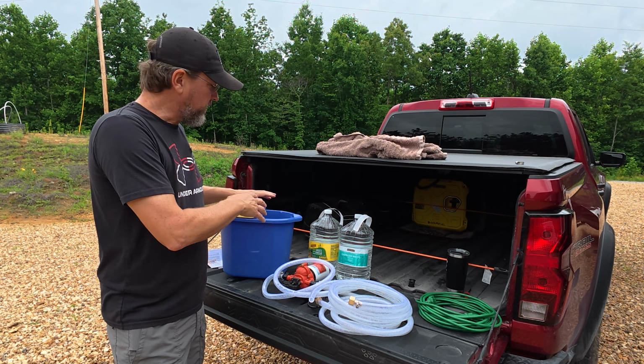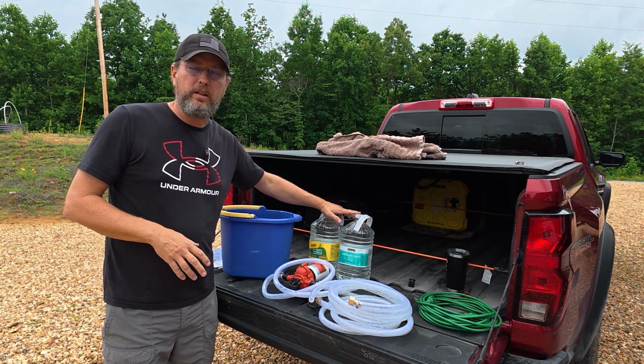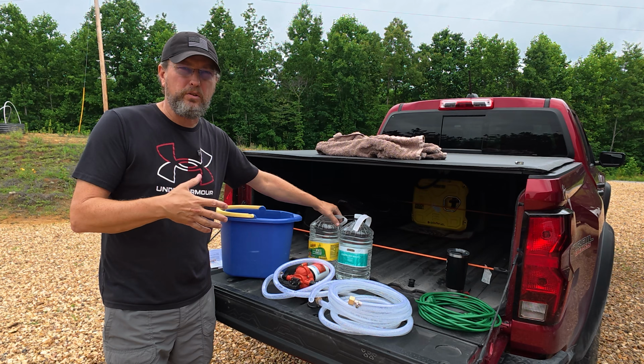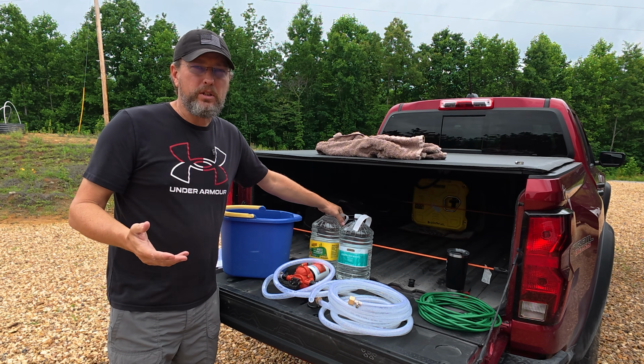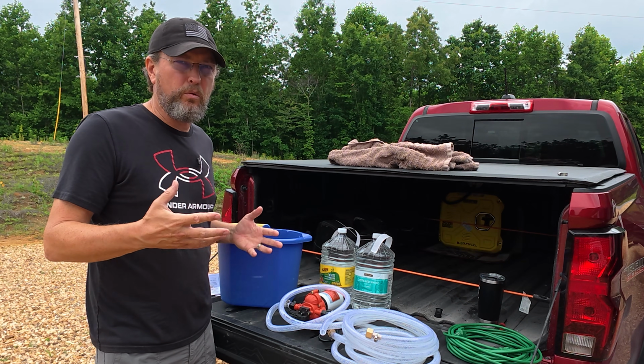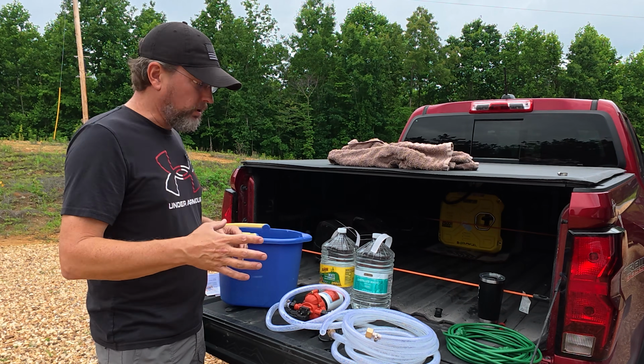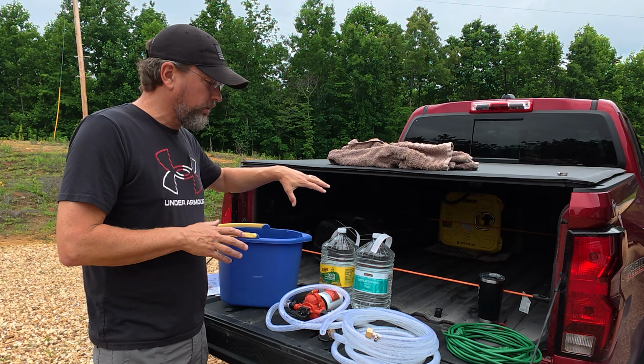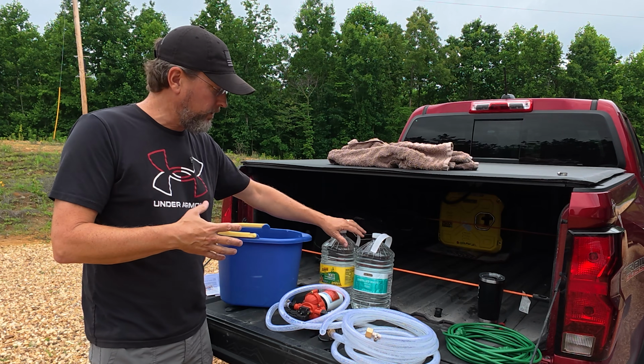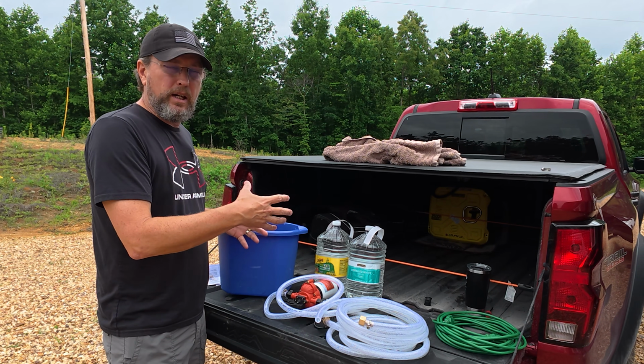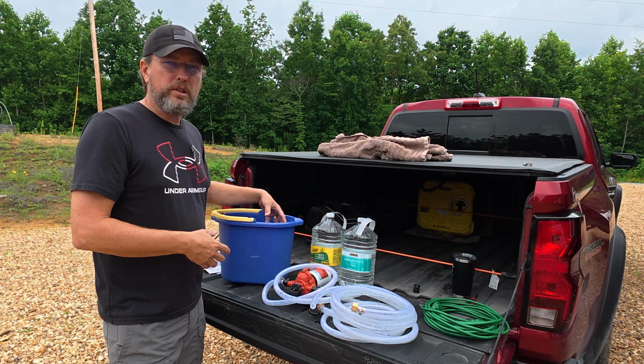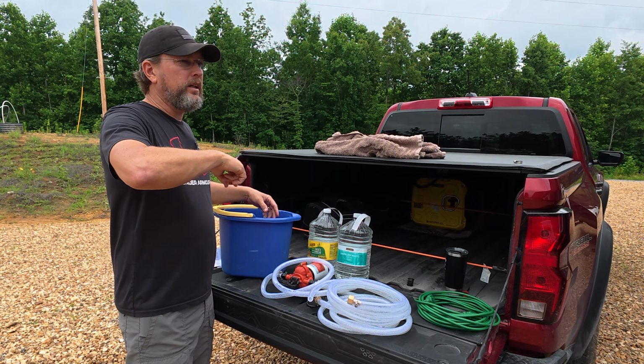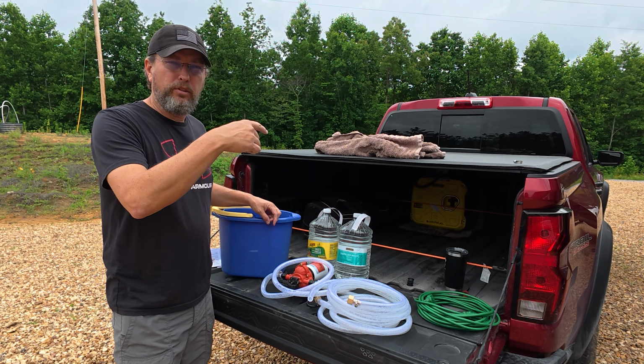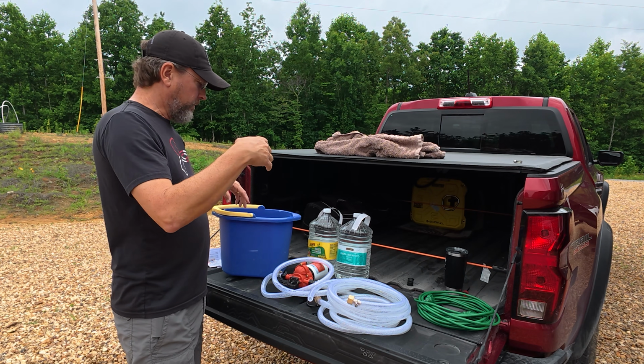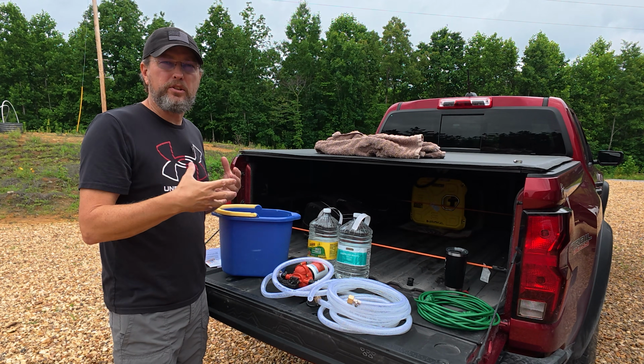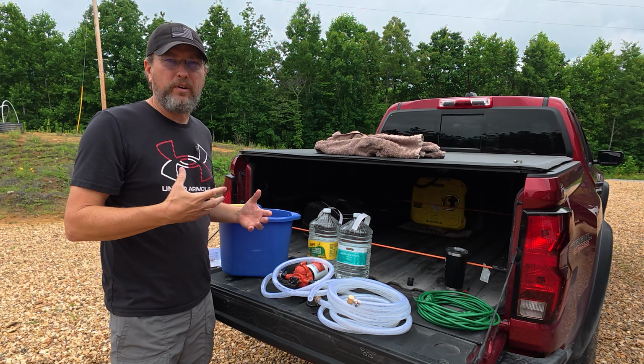Basically, we're gonna fill this bucket with about 2 gallons of white distilled vinegar, which you can get at pretty much any grocery store. That's all we really need. We'll set up this pump assembly so it draws the vinegar from the bucket, takes it up to the water heater, through that heat exchanger, and then back into the bucket. We'll just let it circulate for about 45 minutes.